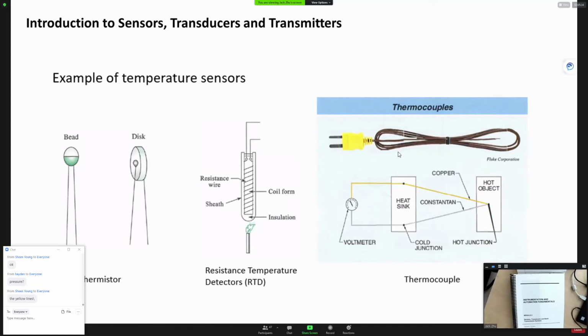In the book, they talk about, I think they call it, active and passive transducers. For the thermocouple, because it can generate a voltage, and voltage is what we call electromotive force, the thermocouple is considered an active transducer. But for this resistance temperature detector, when you heat them up, they just change the resistance of these RTDs. To measure the change of resistance, you need either a multimeter or you have to put in a voltage source, so you can measure the current by giving a voltage through it. If the resistance changes, the current will change. So those types of material are considered passive sensors.